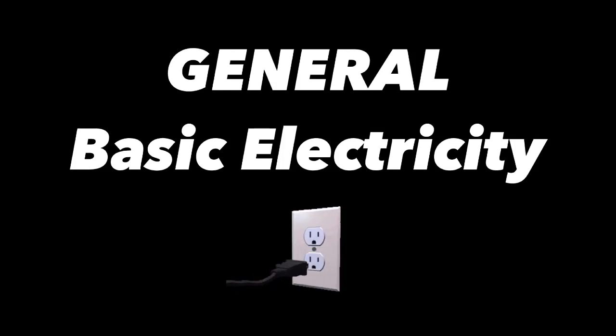What is the range of temperature of an electrolyte in a lead-acid battery that does not require a correction when measuring its specific gravity? Between 70 Fahrenheit and 90 Fahrenheit.